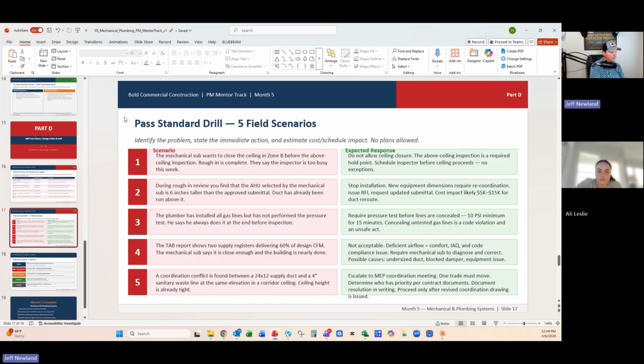And then a coordination conflict is found between the 24 by 12 supply duct and a 4-inch sanitary waste line at the same elevation in the ceiling corridor. Ceiling height is already tight. All right, so hopefully we have found this before anybody did any work. But you're going to have to submit an RFI, and that would go to your design team, spelling out the situation and proposing a solution.